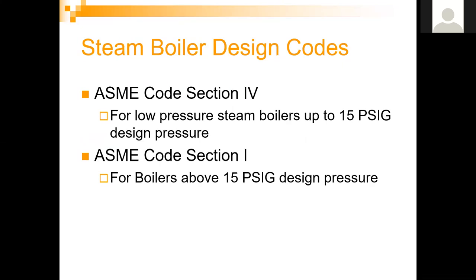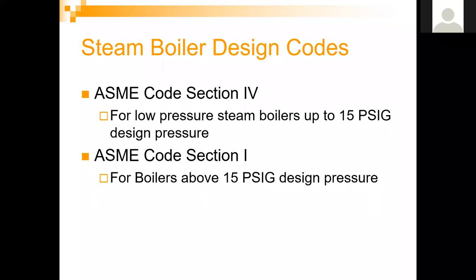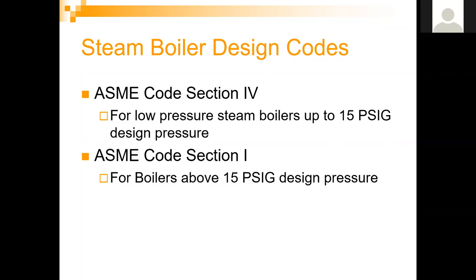Steam boiler design codes: ASME Code Section 4 is for low pressure steam boilers, basically up to 15 PSIG design pressure, meaning a relief valve must be set no higher than 15 PSI. You're really getting a maximum operating pressure of about 10 to 12 PSIG out of those boilers, maybe 13 if you really push it. That's the maximum for a low pressure steam boiler.